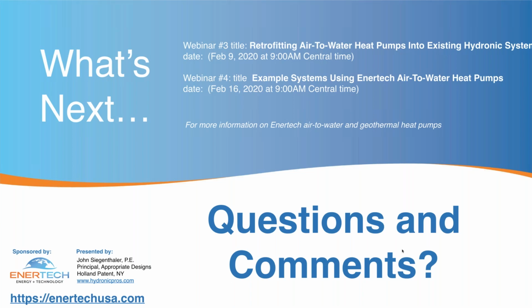Okay, and the last question is, can you compare the SEER rating in cooling for the Advantage versus a high efficiency air-to-air heat pump? Well, there actually is not a SEER rating, a seasonal energy efficiency ratio rating, on an air-to-water heat pump. And the reason for that is it's going to depend on how that heat pump is applied. That heat pump operating at 45-degree chilled water versus, let's say, 55-degree chilled water is going to have a different energy efficiency ratio. So right now, there is no SEER rating on that.